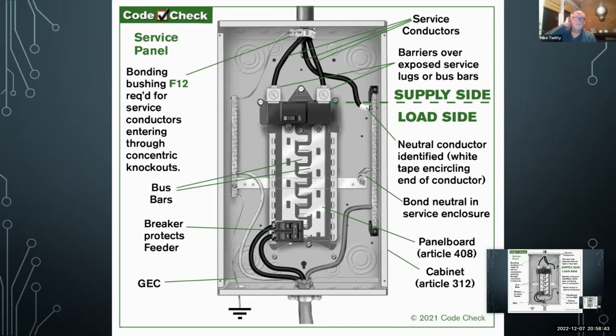I found that out not too long ago. I had done that for years, doing a boat dock installation with a neighbor, and it got called out, and I looked it up, and it's been there forever. But that's just something to know, and that's not that big a deal with home inspectors, but you'll see it sometimes, the smaller gauge wires. So just remember that anything smaller than a number 4 for equipment grounds and neutrals cannot be re-identified with tape or markings.